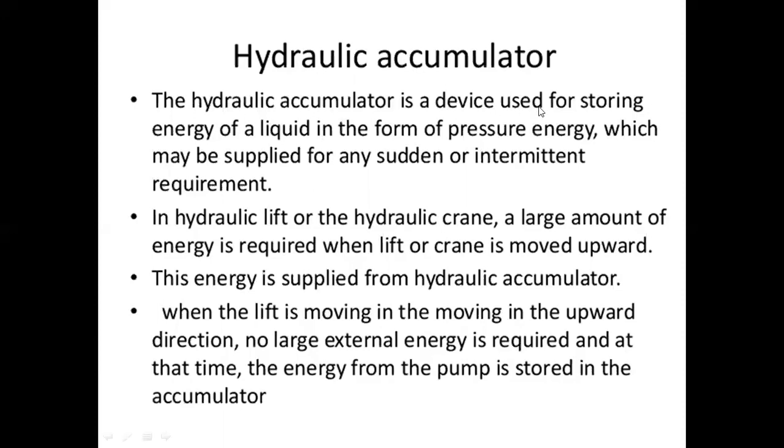The hydraulic accumulator is a device used for storing energy of liquid in the form of pressure energy, which may be supplied for any sudden or intermittent requirement. In a hydraulic lift or hydraulic crane, a large amount of energy is required when the lift or crane is moved upward. This energy is supplied from the hydraulic accumulator. When the lift is moving in the downward direction, no large external energy is required, and at that time the energy from the pump is stored in the accumulator.